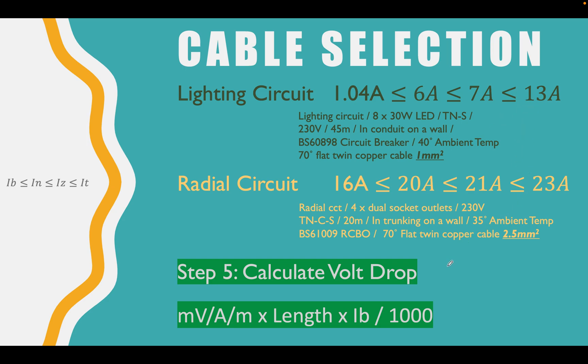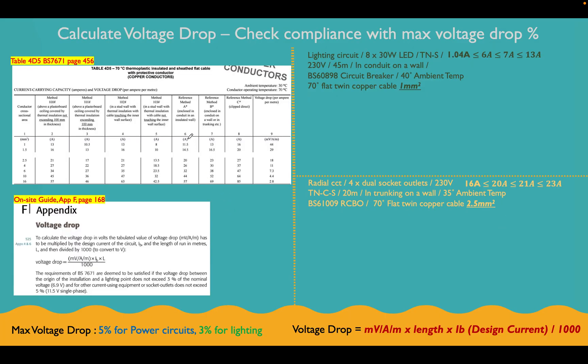So now let's move on to the next slide and we'll go through voltage drop. Okay, so you'll notice this is the same table that we just selected our cable sizes from. This is table 4D5 for 70 degree thermoplastic insulated and sheathed flat cable, which is what we're using for both of these circuits. This is from table 4D5 in BS 7671, the big brown book. We've also got this down here from the on-site guide, the appendix F, which is a bit of information about voltage drop.